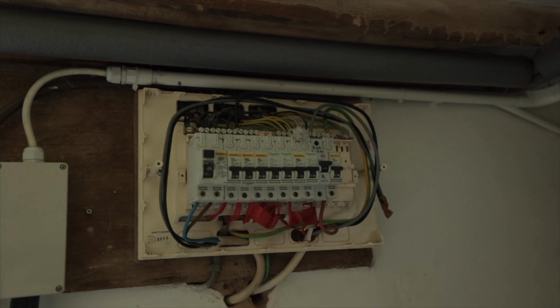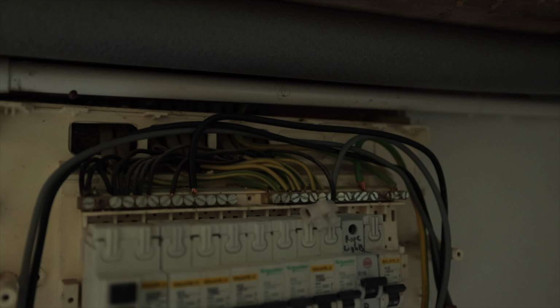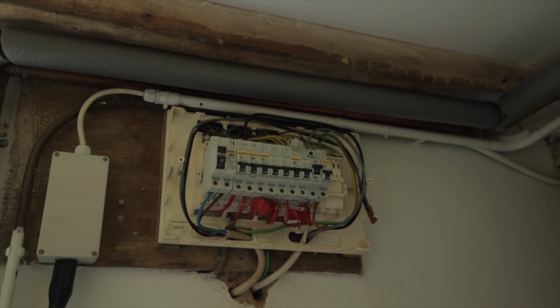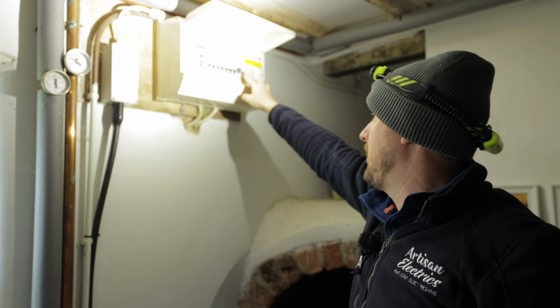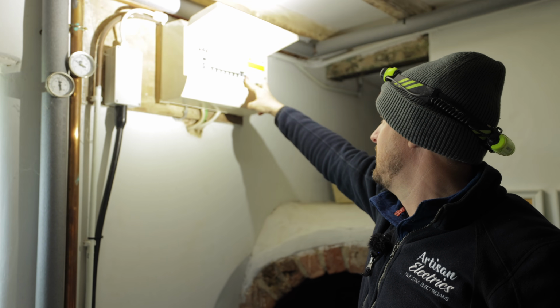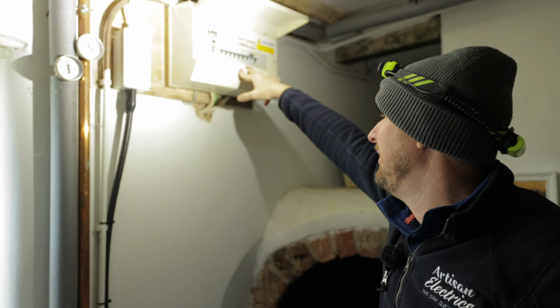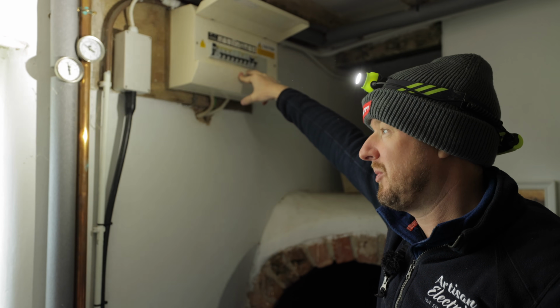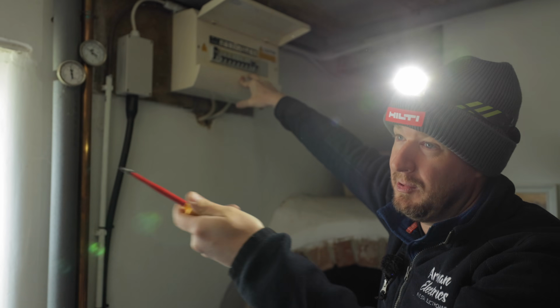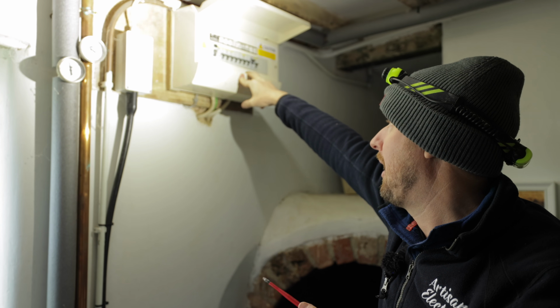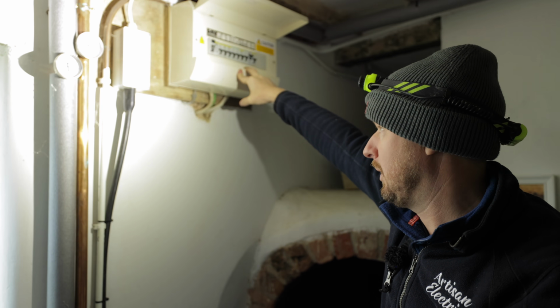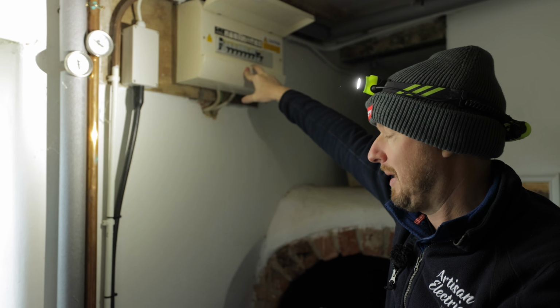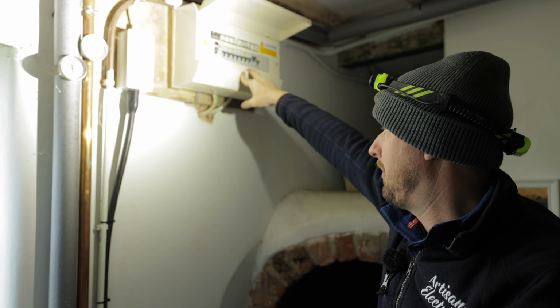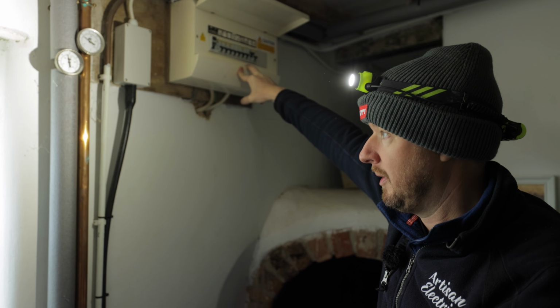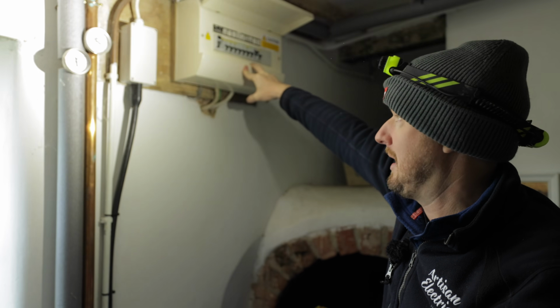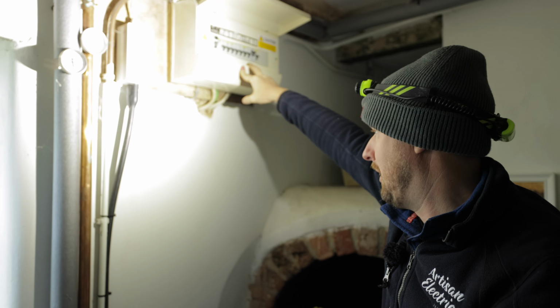The good news is the wiring looks like it's in decent condition. I'll probably recommend an EICR anyway since they've not had that done, and then we could possibly upgrade this consumer unit to a modern one and upgrade the supply to the extension, because it's way undersized. The feed to this building is only 6mm, and although we could potentially double up the cores and give ourselves 12mm, with the volt drop and the fact the cable's not buried properly, I'm just going to recommend upgrading the cable to a much bigger one. It future-proofs it if they ever need to increase capacity. It's safe, it's properly buried, there's no issues with volt drop, which with generators can be quite a challenge anyway, and it just makes the whole setup much more resilient.